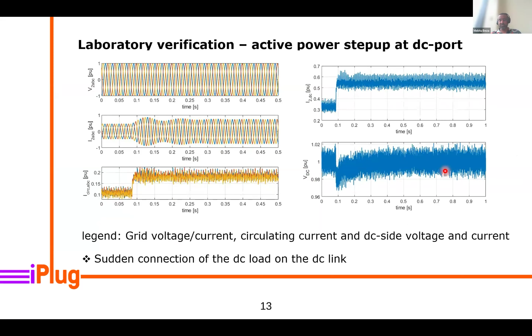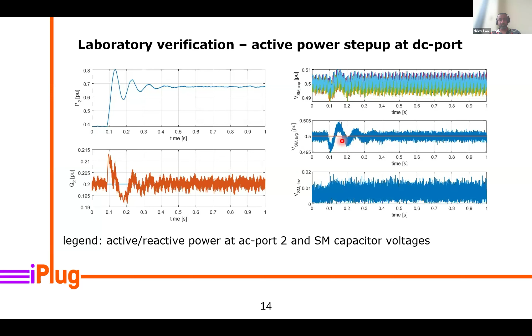And we could see that the sub-module capacitors are balanced within range, which shows that the operation is possible. But we could see that there's a low oscillation in here in the power step on AC port 2. And of course, that's natural due to the high capacitance we use in a multi-level configuration for the multi-level converter.